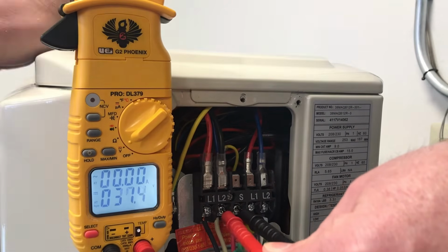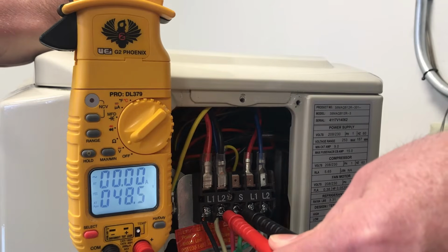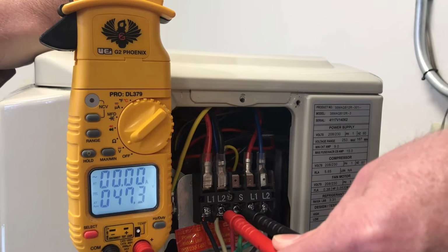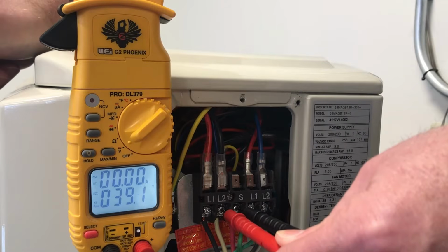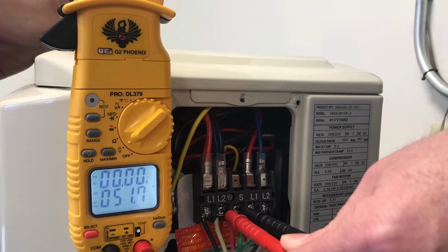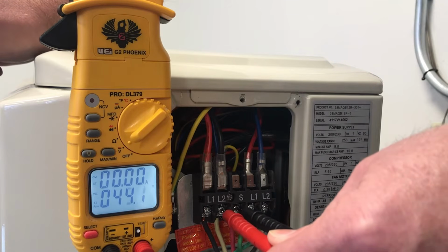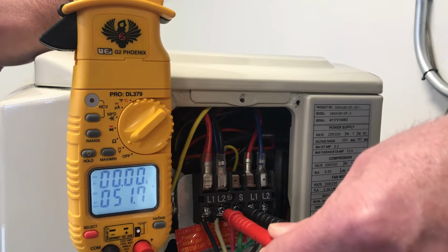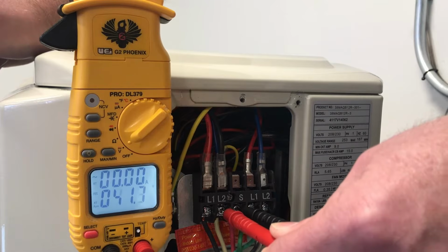If that negative never pops up, what that's telling you is that you have a possible issue with your outdoor unit. You're not getting communication to the indoor unit. Your indoor is sending a positive signal out. The negative signal from the outdoor unit is not getting received back. So with that, we have to go and check the outdoor unit to see if there's either an issue with the wire or possibly an issue with something outside.